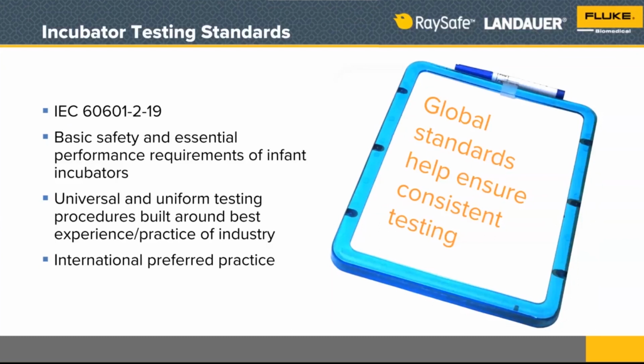Here's the standard that we were talking about. Under the IEC 60601 umbrella of minimum performance and safety standards internationally, 60601-2-19 covers infant incubators that are used in the hospital in a level 2 neonatal nursery or a neonatal intensive care unit. There are two other standards also. The other standard for infant incubators is 21, I believe, which is about transport incubators. Those transport incubators integrate ventilators and other medical devices all together in one unit.